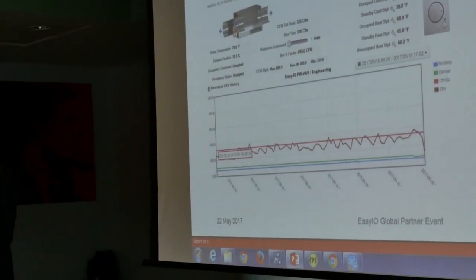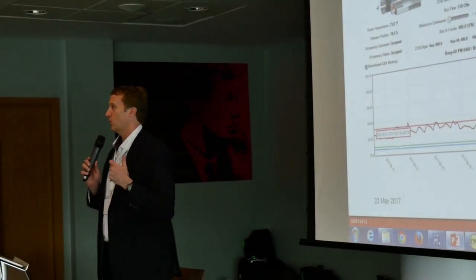A, you'll wear out the actuator, and B, your flows are going to be turbulent. If they didn't give you the four straight duct runs in front of the box, you'd have a turbulent inlet. Or if the static's not maintained dead on from the air handler, static can go up and down, and the last thing you want is that actuator constantly chasing that, right? You want it to get within the CFM flow set point, and then hold, right? Stop hunting around. So we built a special PID that has those features in it.